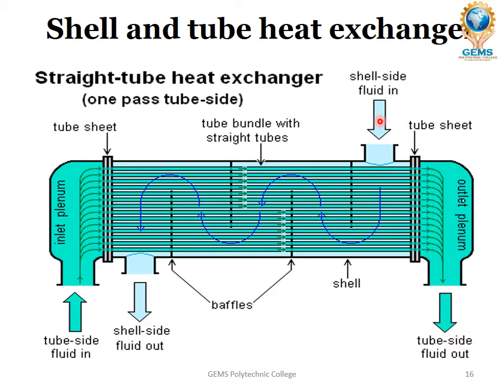And this entry is for shell side fluid in. This fluid enters the shell side, so that this fluid goes over the outer surface of the tubes. Once it goes in, it comes out this way. In between, they provide some baffles so that more transfer may occur, so that the fluid may settle for a short time and more transfer will happen.